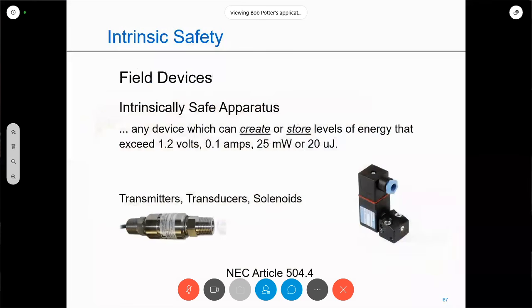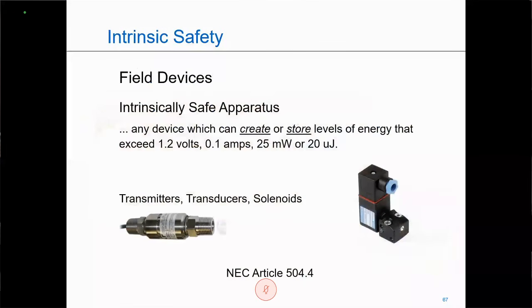Now, when it comes to my field devices, if these devices can generate and store energy, and here are just a few examples, that device within itself also has to be intrinsically safe and rated, because we have to make sure that this device does not become the ignition source. You'll notice here this gland, light blue. Light blue is a common color that's associated with intrinsically safe wiring.